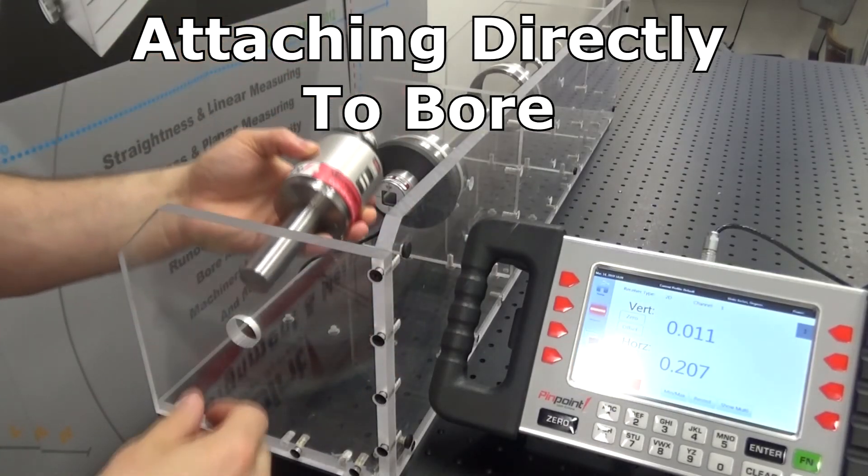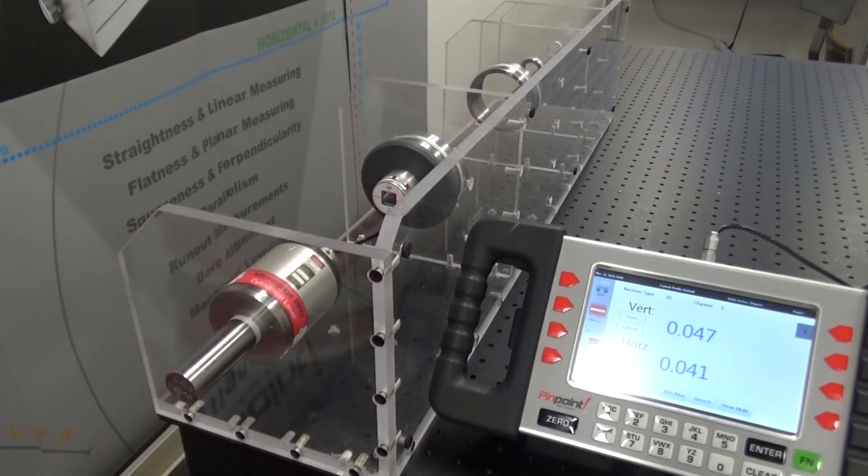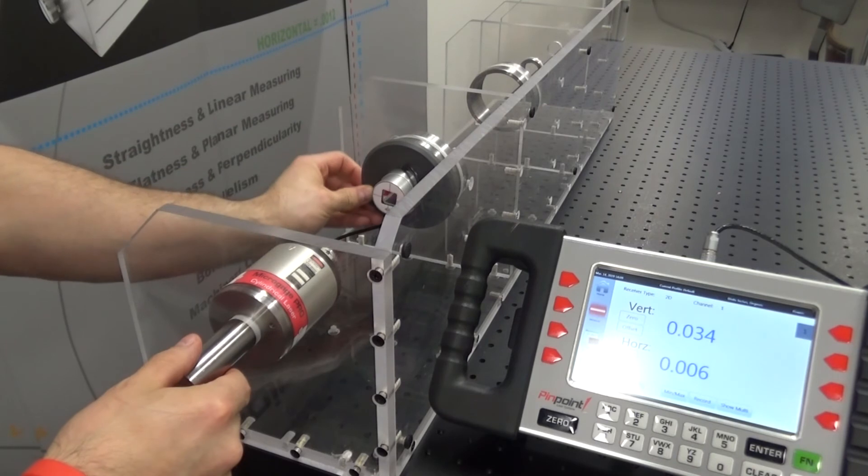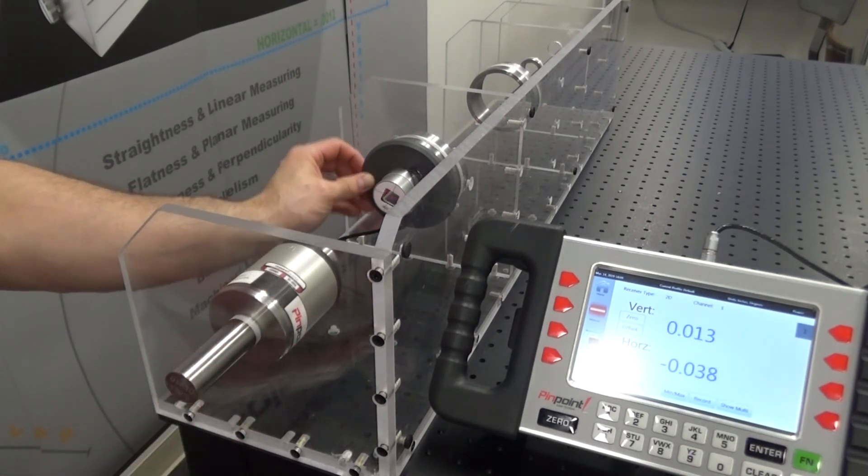Another option is to attach the cylindrical laser directly to a bore to create a precise straight reference datum line. By rotating the laser and receiver and averaging measurements, any mechanical errors in fixturing can be averaged out and the true center of rotation can be calculated.